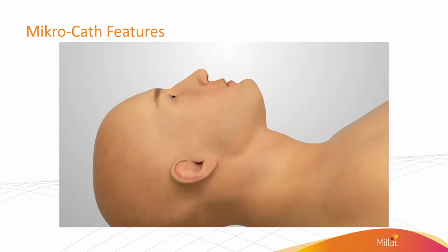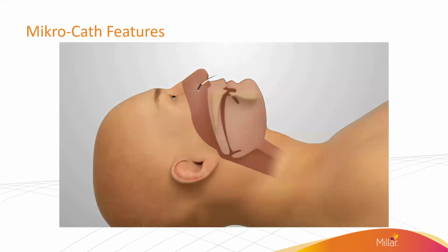Millar's Mikro-Cath is a 3.5 French or 1.17 millimeter diameter solid-state pressure transducer with a sensor side-mounted at the distal tip. The catheter is 120 centimeters in length and made out of flexible nylon. The small diameter plus the flexibility of the catheter lessens discomfort when placing the catheter in the patient. With the Mikro-Cath, researchers and clinicians can gain insights into airway physiology by studying minute air pressure changes in the pharynx, larynx, and even pleural spaces for up to 24 hours in a patient.